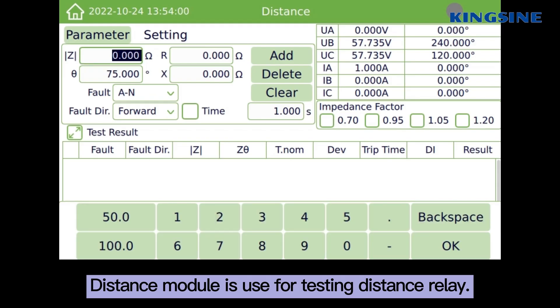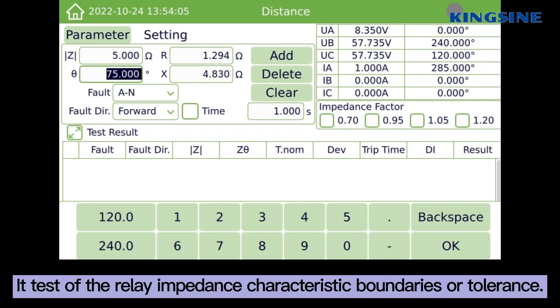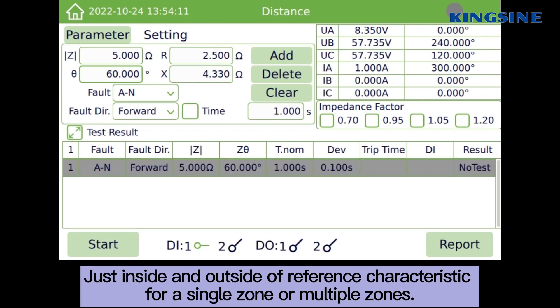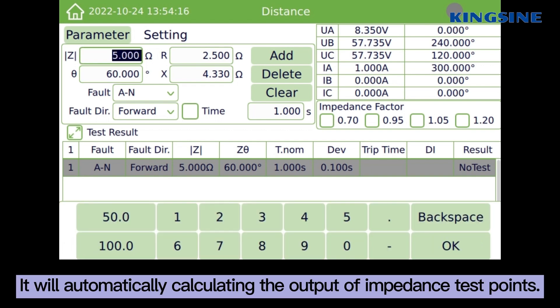Distance module is used for testing distance relay. It tests of the relay impedance characteristic boundaries or tolerance, just inside and outside of reference characteristic. For a single zone or multiple zones, it will automatically calculating the output of impedance test points.